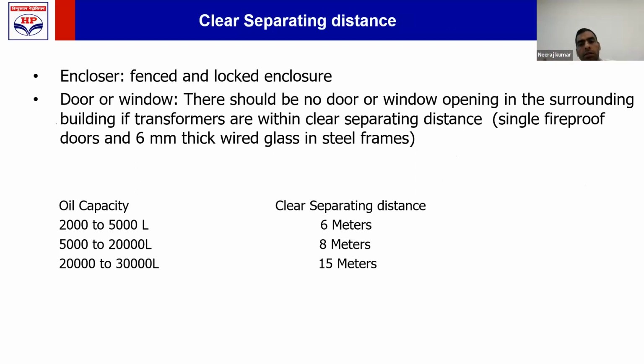Then in that case, that door which is coming in this distance, 6 meter, 8 meter, 15 meter, whatever it is as per oil capacity, shall be a fireproof door. चलो डोर नहीं आया, एक छोटी सी विंडो आ रही है. Then that window shall be 6 mm thick wired glass framed in a steel frame. So there will be a steel frame in which 6 mm thick wired glass shall be put. Then you can put a window.